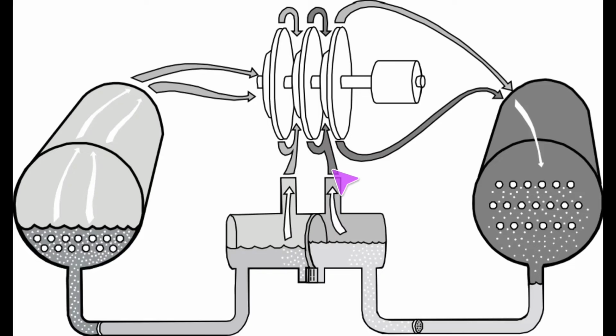So what you're looking at here is a 3-stage design. Okay, it's basically the same picture, but there are just a couple of slight differences. Obviously, first and foremost, the CVHE series is going to have this third impeller here. So you've got stage 1, 2, 3. Each of these stages feeds into the next, and it's just pushing through. Again, you're going to have a guide vane here, and a guide vane here, and everything else about this basically functions the same. It just has one additional impeller, and you'll be able to see it visually on the compressor.